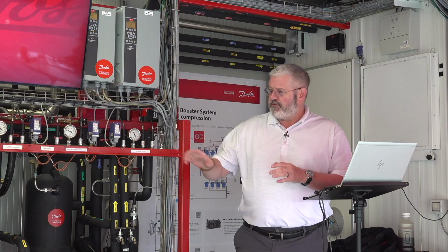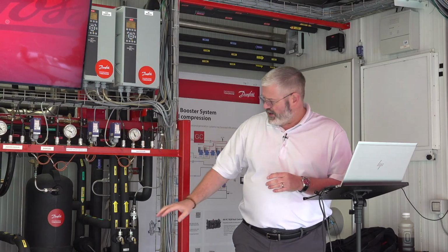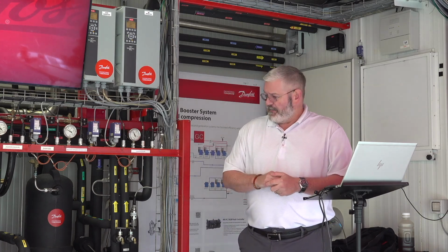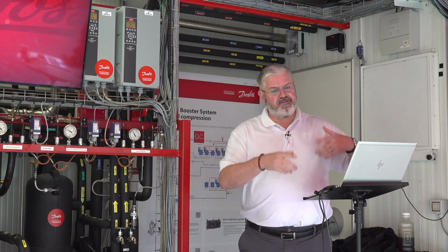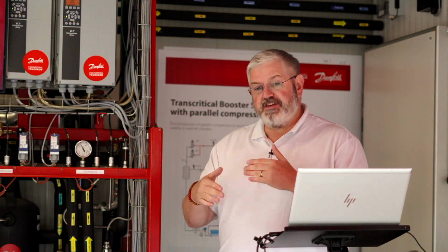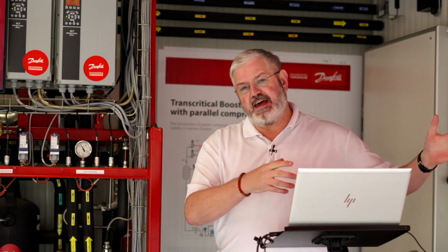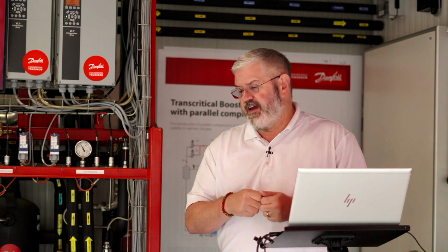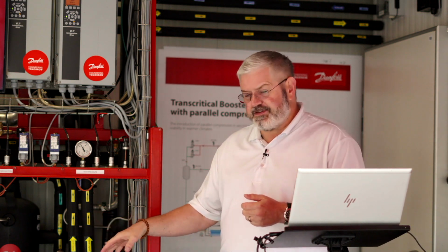So you open your valves. We would open our high pressure valve, our receiver bypass valve, our expansion valves, and you want to charge the system with vapor up to roughly 100 pounds so that you get above the triple point and you don't make dry ice. Once you're above 100 pounds, you would then add liquid to the system, turn on one of your evaporators, and you get some load going, and you continue to add liquid as the store side of the system, the evaporators, take it away. Keep charging with liquid, get your compressors running.